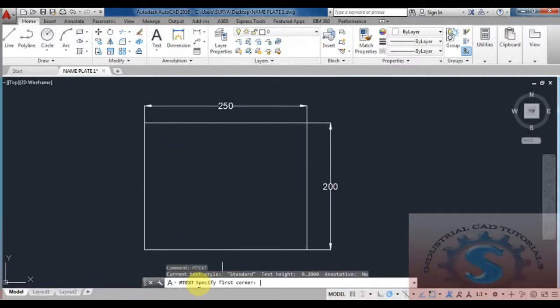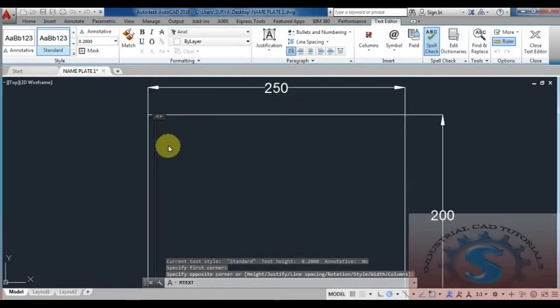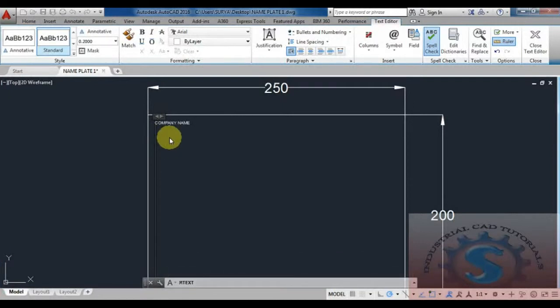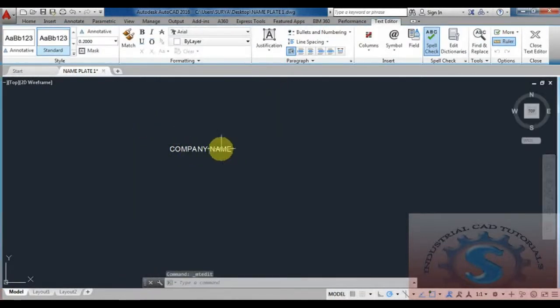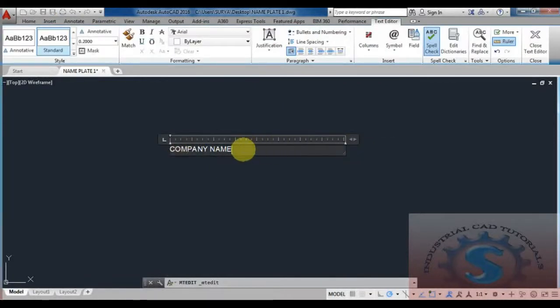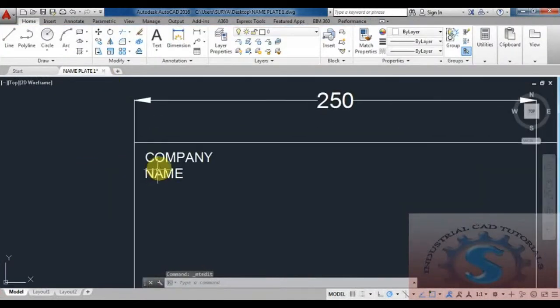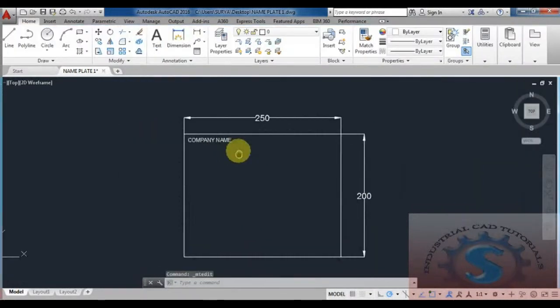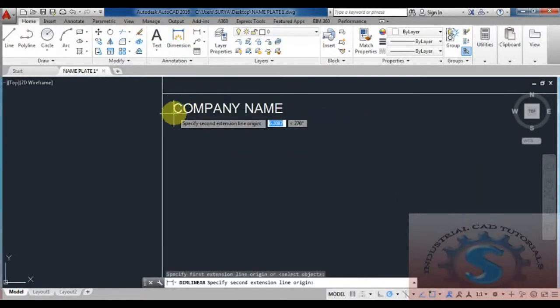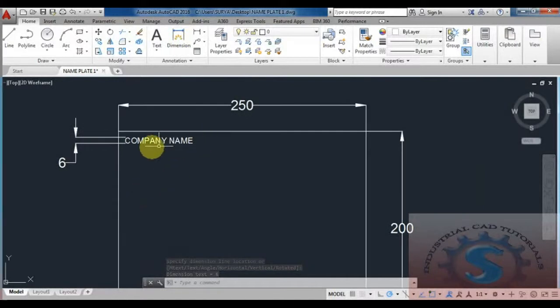Next, use the MTEXT command — type MTEXT and enter. Specify a point on the inside and give the name you want. First, add the company name on the nameplate. The size of the text should be 6.0 mm. This is the minimum requirement; you should follow these dimensions. The minimum text height for the company name should be 6 mm.